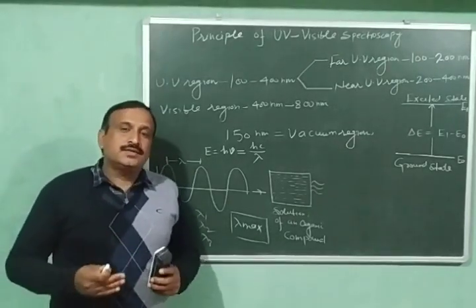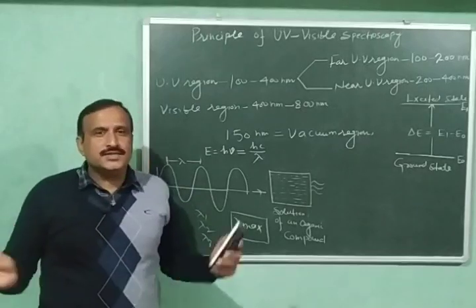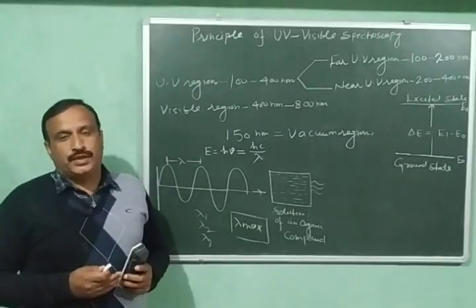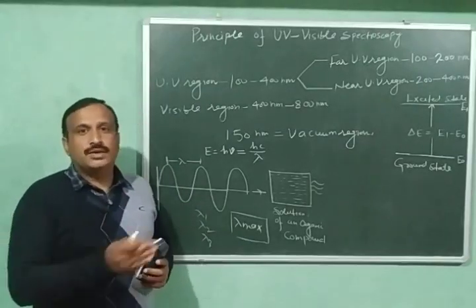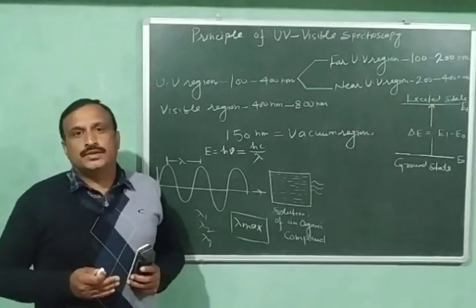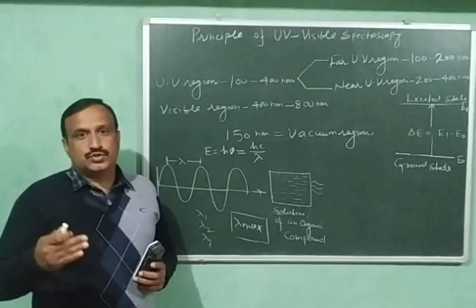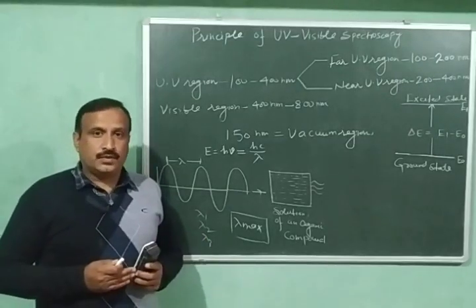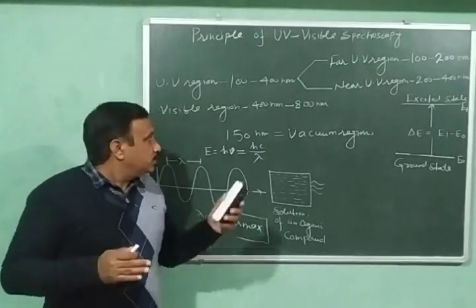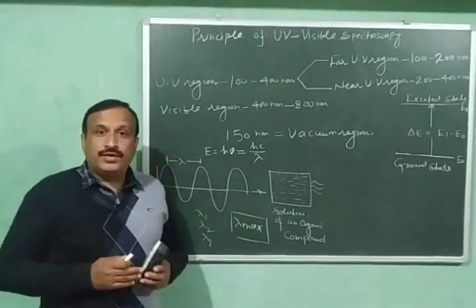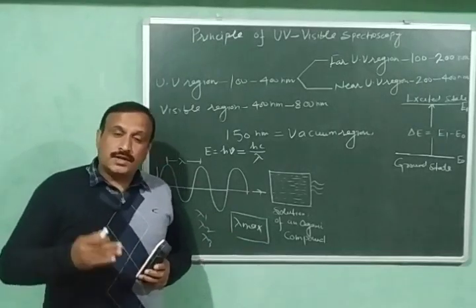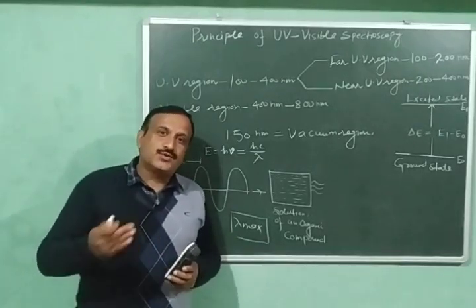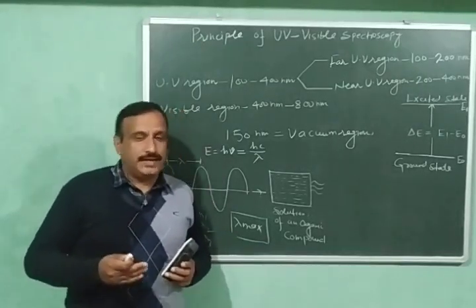So measurements in this region are done by flushing the instrument with nitrogen. Then the oxygen will come out of the instrument and nitrogen will be present inside it. However, below 150nm nitrogen also starts absorbing UV radiations.